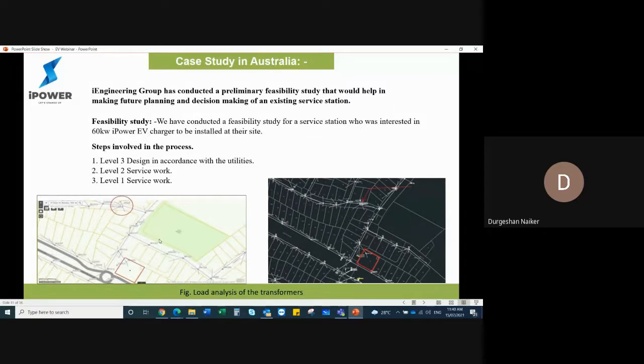In the worst case scenario, if you don't have capacity, that means you may have to upgrade the transformer, and you may also have to upgrade the LV conductor coming to the supply point on the site. So that becomes pretty much utility design work, which can be done by companies like iEngineering, who are authorized to work on the HV network.